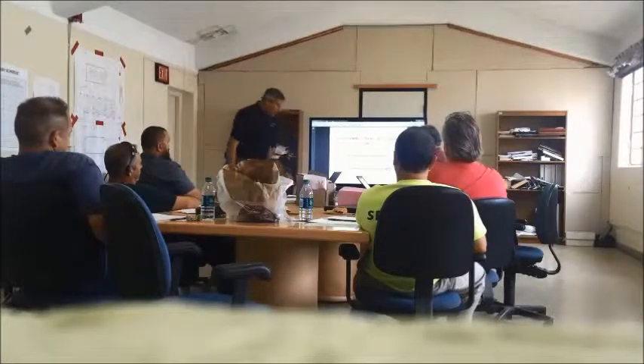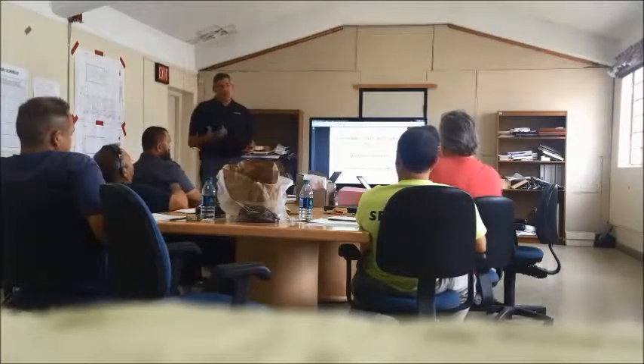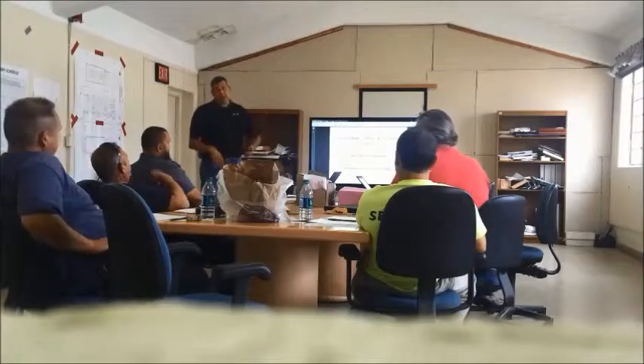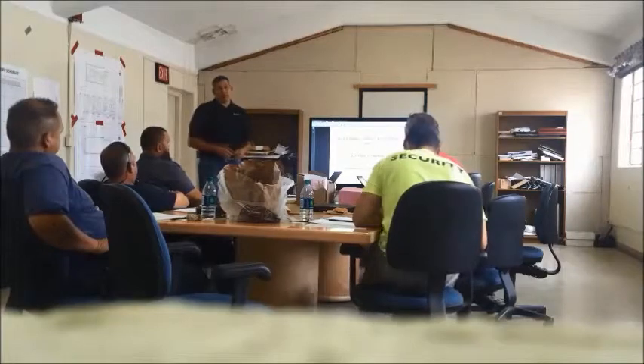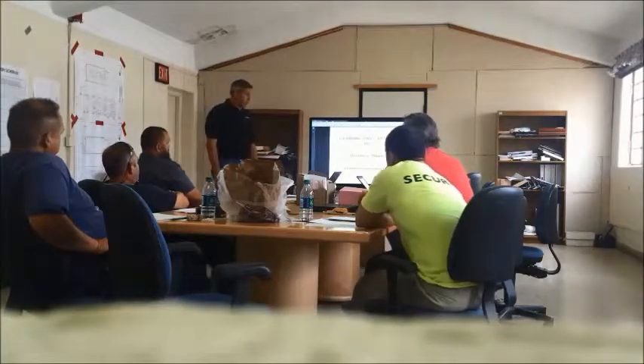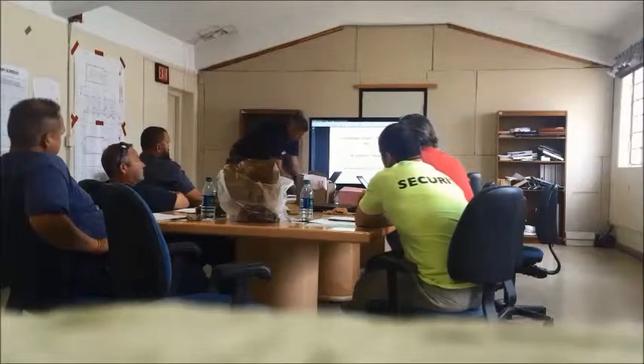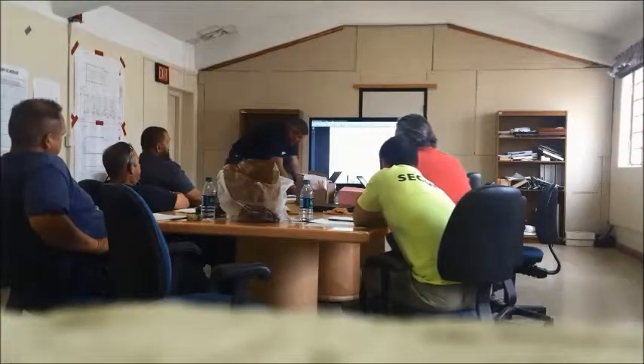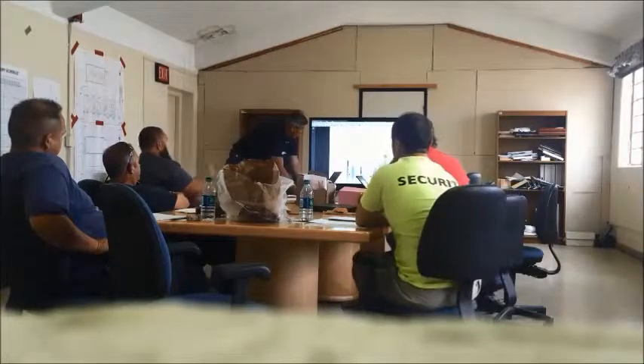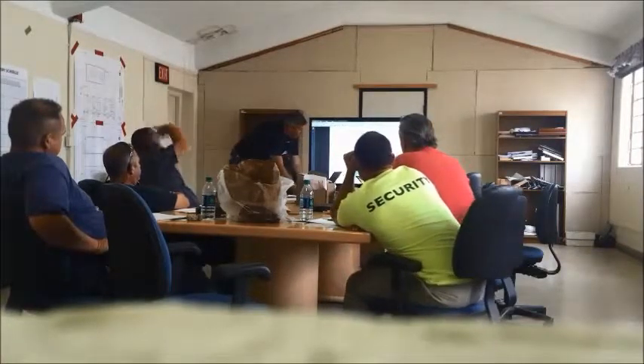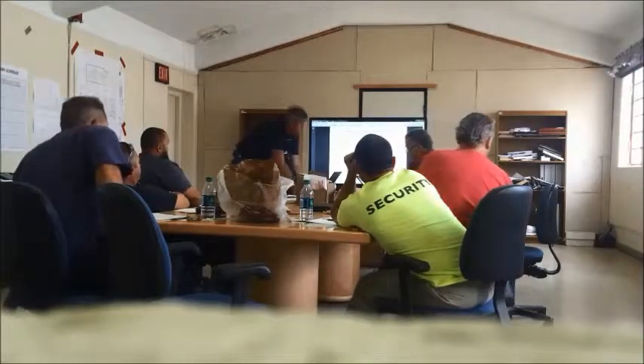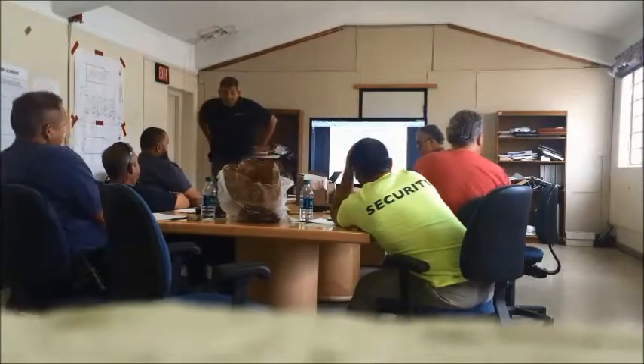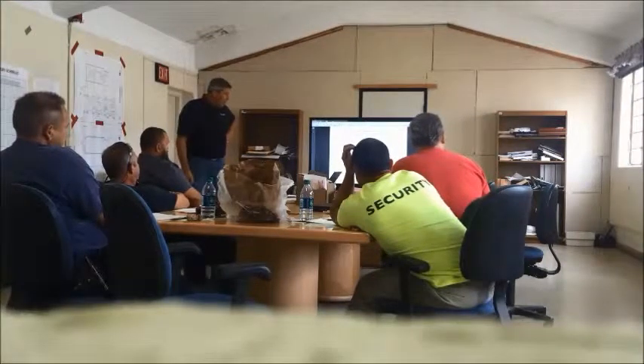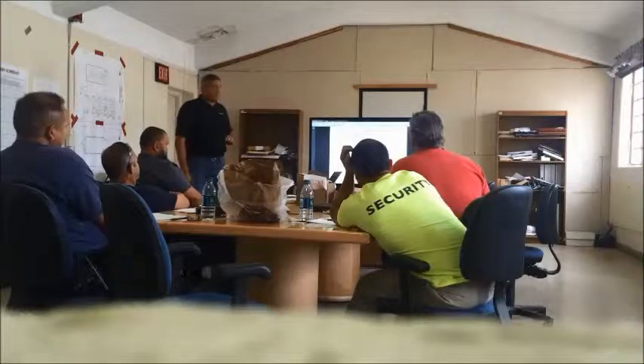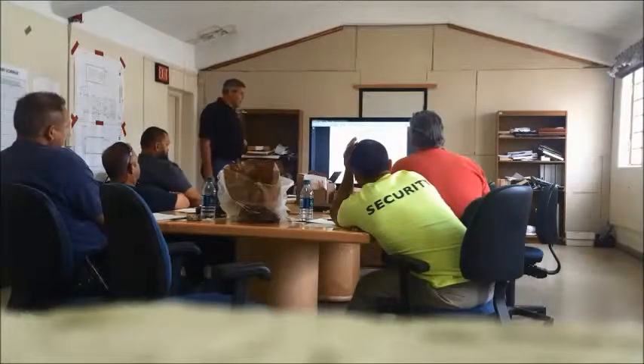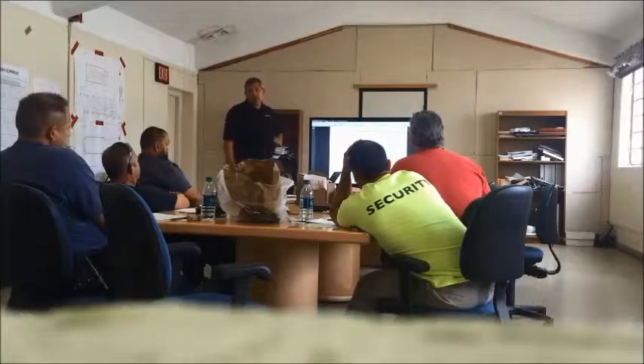Next section was VFDs, and we touched on Danfoss and ABBs. I don't know if you guys have any questions. You have the manual buttons to push and to run in hand. Obviously, all of them should be running on automatic, it's normal condition, normal mode. We do have two styles. You have your standard ACH 550 drive with bypasses. They're outside, obviously, they're NEMA 3. Inside the air handlers, might be NEMA 1. But again, all air handlers have Danfoss, and the exhaust system and the pumps have ABBs, but they all have bypasses.